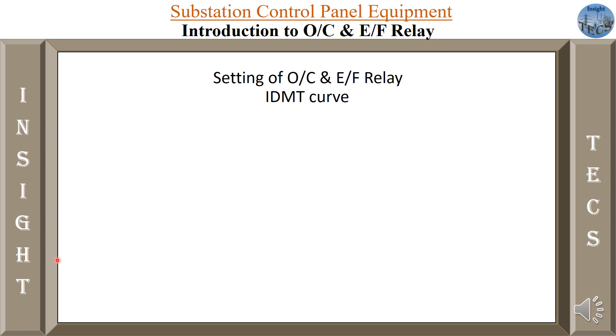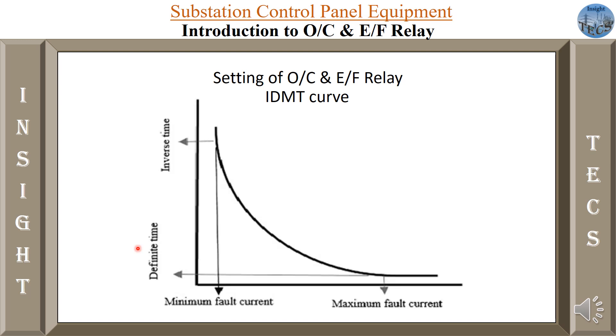Now for settings of over current and earth fault relay — a very interesting topic. To understand the settings we first have to understand what is the IDMT curve. IDMT basically means Inverse Definite Minimum Time curve, which is used for doing the settings of this relay. On the x-axis there is current and on the y-axis there is time. When the current is less, the time taken by the relay to operate or send the trip command is more. As the current increases, the time taken by the relay to operate is minimum — as the name suggests, inverse definite time.